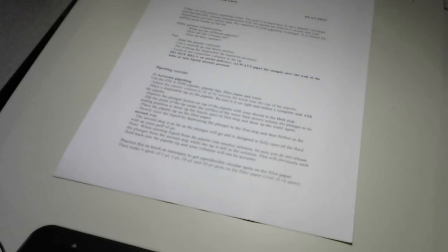You see this is going to 50 microliters. So the minimum it will pick up is 20, so the bottom number will make sense in this pipette. It will not become red. That means you have to pay attention to the bottom number on this. So the minimum it can go is 20. That's the minimum this pipette can pick.